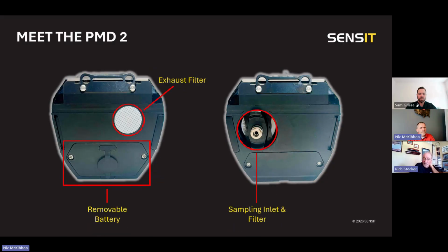On the sides of the unit, on the inlet, there's a three-quarter turn twist on the filter housing, and the filter is easily removed and just twist locks into the cap. It's a pretty simple change out for anybody that sucks water or dirt up into the unit itself. We can change that filter very, very quickly and easily. On the left side of the screen there is an exhaust filter to keep dirt and junk out when the unit's not being used in the field. And our battery is removable as well. The batteries are chargeable, either installed in the instrument or outside of it, so that in a remote area where there's going to be maybe a double shift or longer in surveying, we can quick swap the batteries and be up and running, even if we exceed the battery life of a single battery.